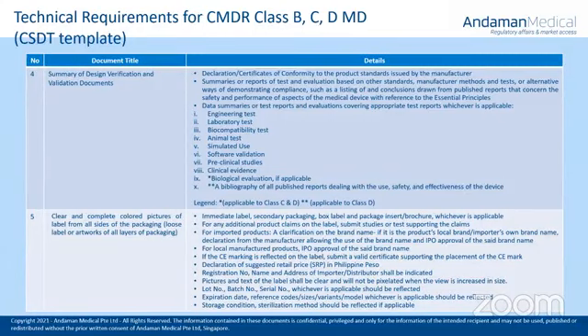The next requirement is the summary of design, verification, and validation documents. So this section should contain design verification and design validation data to the extent appropriate to the complexity and risk classification of the medical devices. It should include the declaration of conformity.